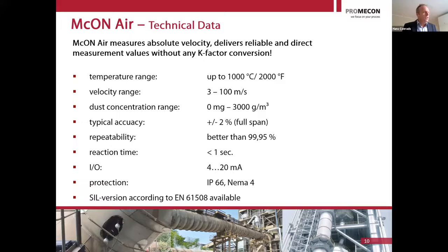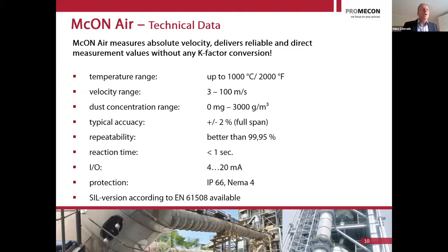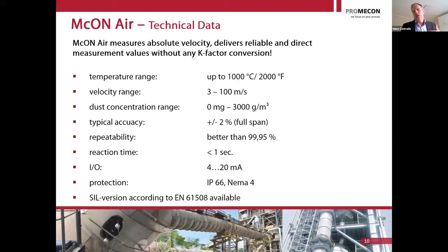Typical accuracy depends on the ducting. If we have a long, straight duct such as a downcomer, it's not a big deal — you have a fairly flat flow profile due to high velocity. For short ducts, such as exits from raw mills or cement mills, we are happy to perform a CFD calculation to determine whether one measurement location with our sensors is sufficient, or whether two measurement locations and averaging would be advisable.